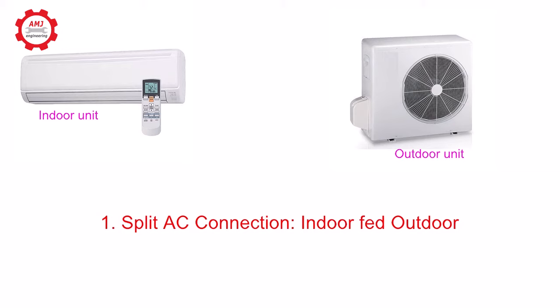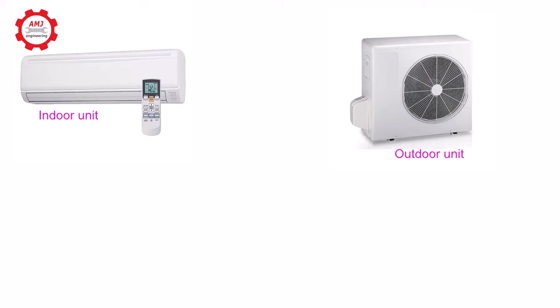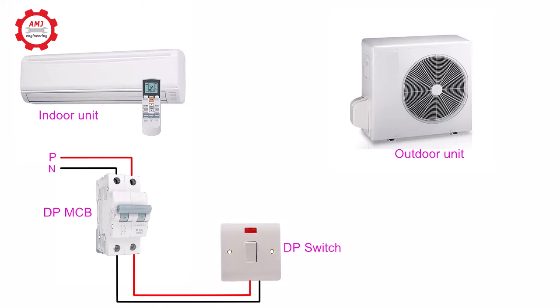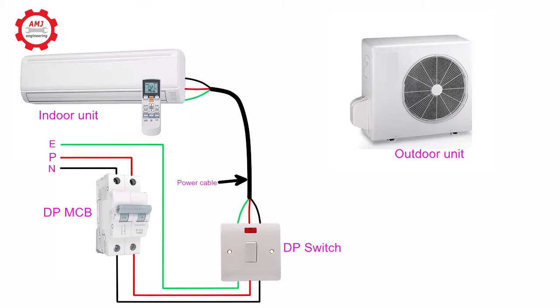The connection diagram is as below. First, the power supply comes from the main distribution board and goes to the double pole MCB. After the MCB, the supply goes to the double pole switch. After the switch, the power cable of the air conditioner starts. The power cable of the air conditioner contains three wires: phase wire, neutral wire, and earth wire.